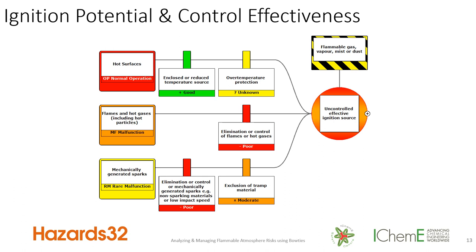The advantage of bowties and the barrier thinking associated with them is that you can show much more information. You can show the likelihood or potential for each type of ignition source — whether it may only occur rarely when you have an equipment malfunction, or may be common as part of normal operation. You also show the effectiveness or performance of the control measures or prevention barriers — whether they are good, very good, or poor — based on your evidence, maintenance records, audits, and records, to give a sense of the robustness of your protection portfolio.